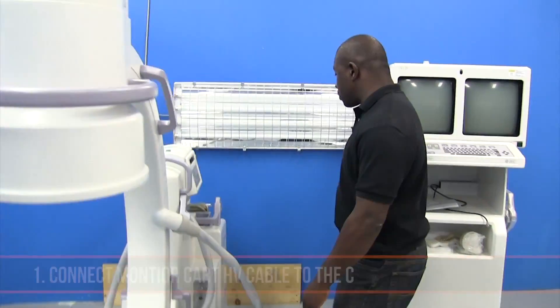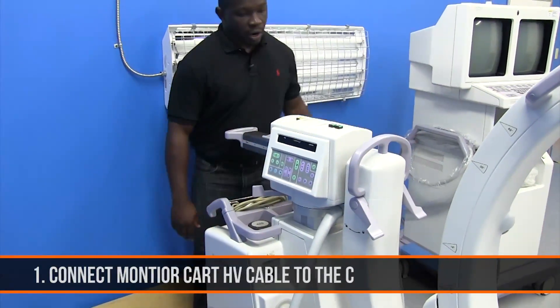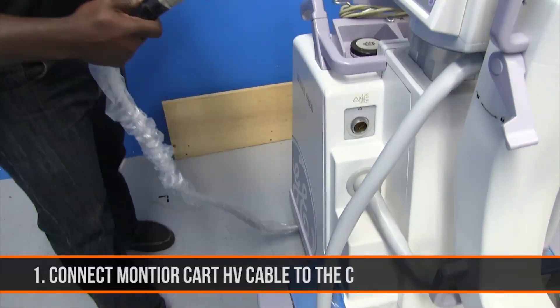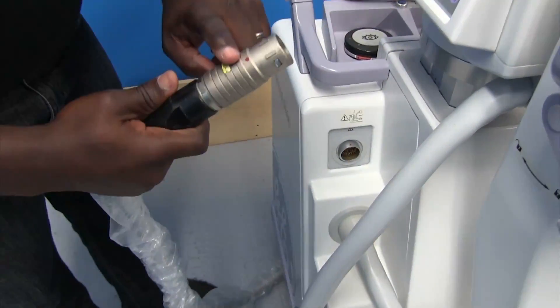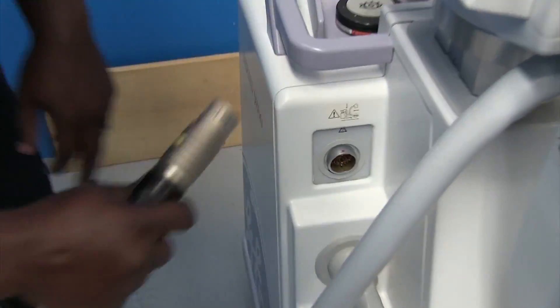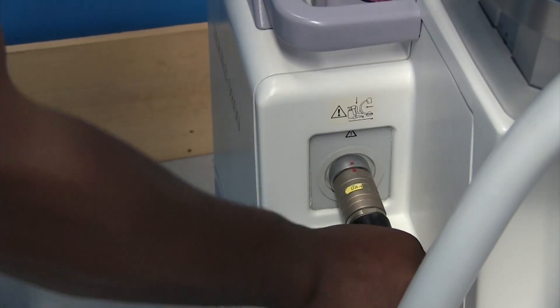Hello. I want to take a few moments to show you how to power up your C-arm. First, your HV cable that's running from your monitor cart to your C has to be connected. There's a red dot that indicates on the end of the HV cable that goes to a red dot on there.